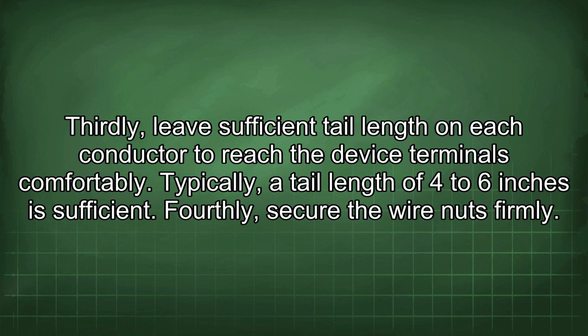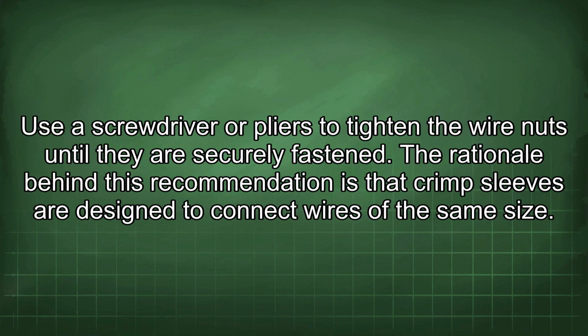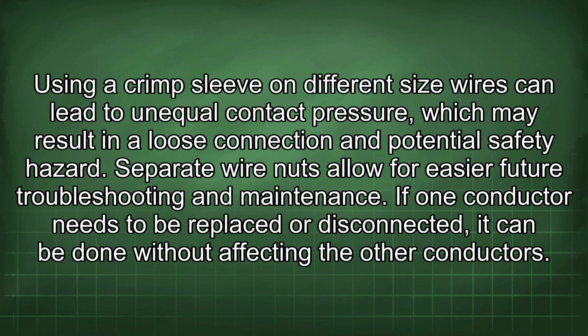Fourthly, secure the wire nuts firmly. Use a screwdriver or pliers to tighten the wire nuts until they are securely fastened. The rationale behind this recommendation is that crimp sleeves are designed to connect wires of the same size. Using a crimp sleeve on different size wires can lead to unequal contact pressure, which may result in a loose connection and potential safety hazard.